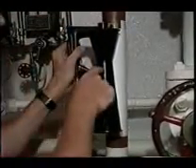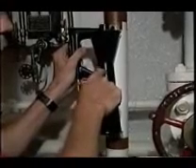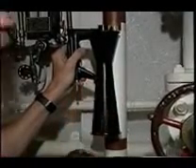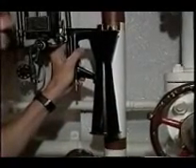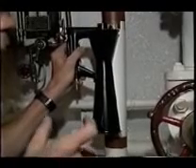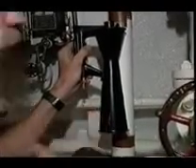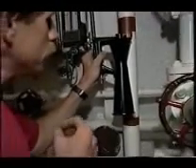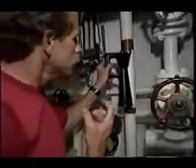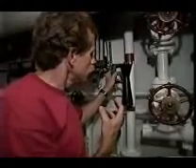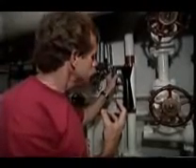Now the advantage of a venturi is that it doesn't cause as much pressure drop as a simpler device such as a simple orifice. These differential pressure techniques are very nice in that there are no moving parts, so they're very reliable and fairly inexpensive. The disadvantage is that they typically have a limited dynamic range, or range of flow rates where they're accurate, and they cause a pressure loss in the system.